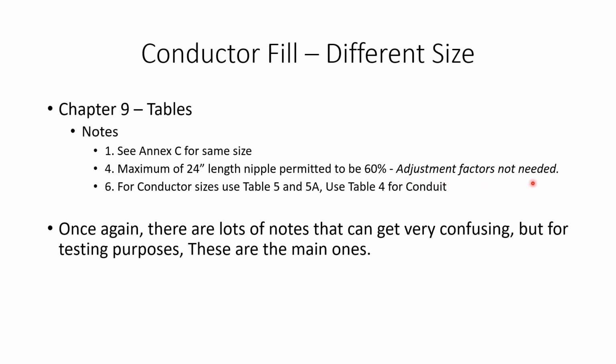Remember we talked about the adjustment factors for the ambient temperature being different than 86 degrees Fahrenheit or more than 3 current-carrying conductors, you need to do an adjustment factor. Guess what? You don't need to do those adjustment factors if it is a maximum 24-inch nipple as well. I don't think I put that in that video. You don't have to do the adjustment factor if it's a nipple, 24 inches or less.